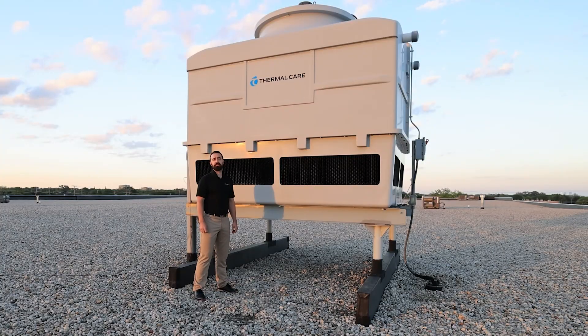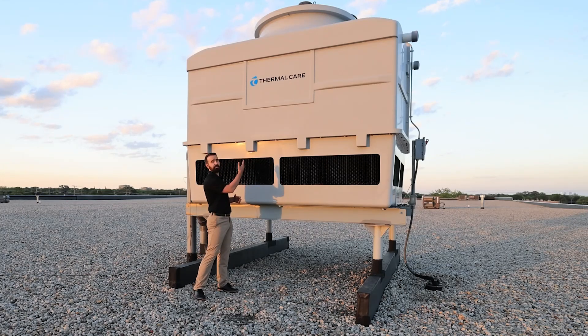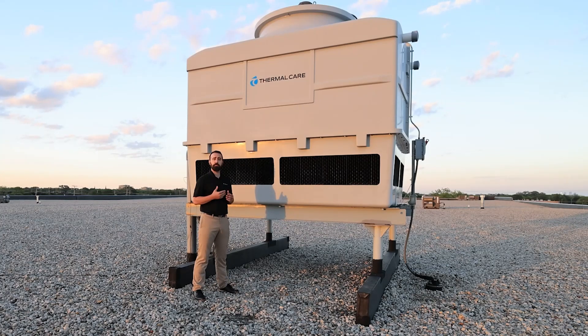All of Thermal Care's cooling towers use a direct-drive fan with a TEAO motor — that's a totally enclosed air over — so it's protected from the elements and it uses the air it's already pulling through the system to cool that motor. That also includes permanently sealed lubricated bearings, so there's no maintenance required to routinely add lubrication.